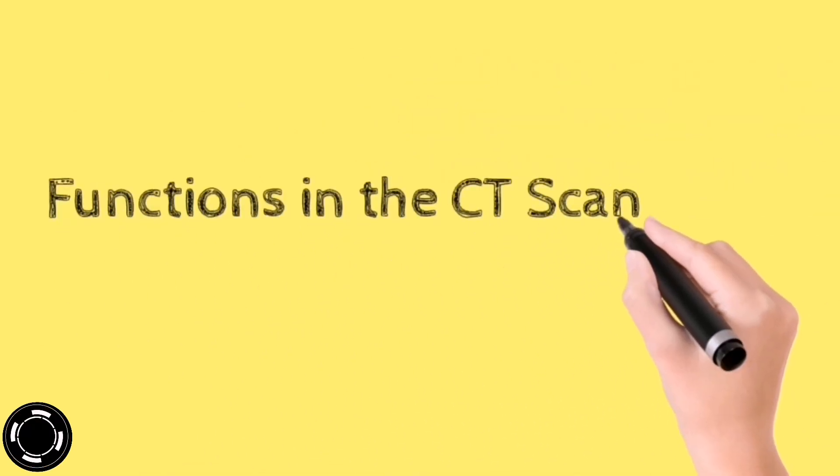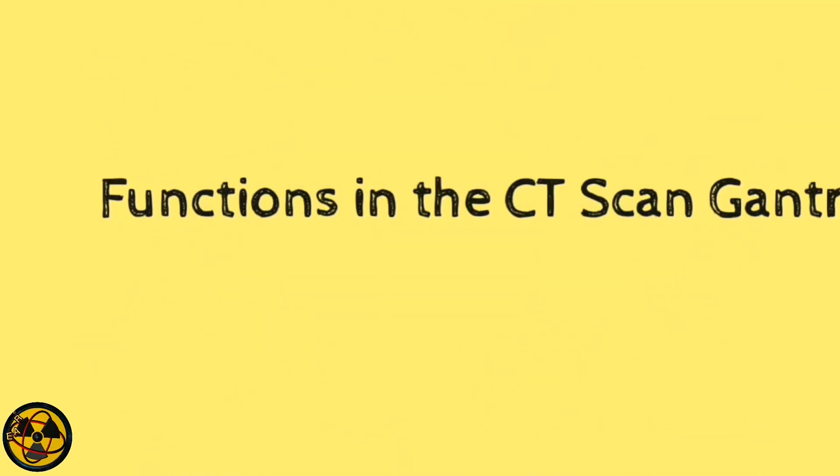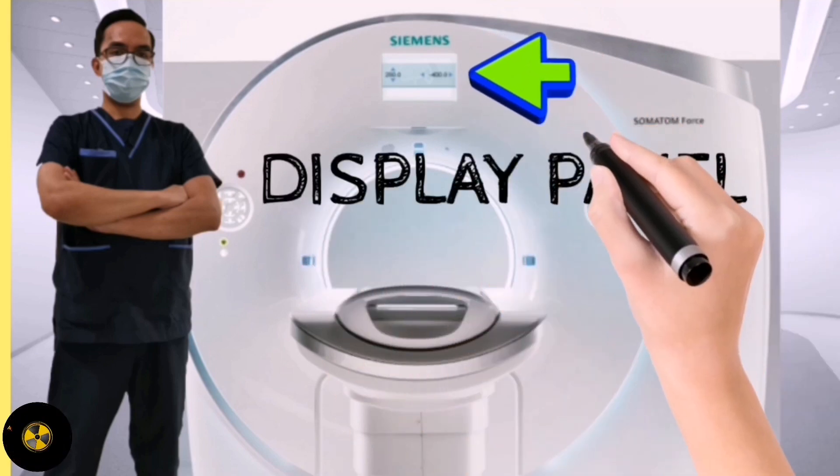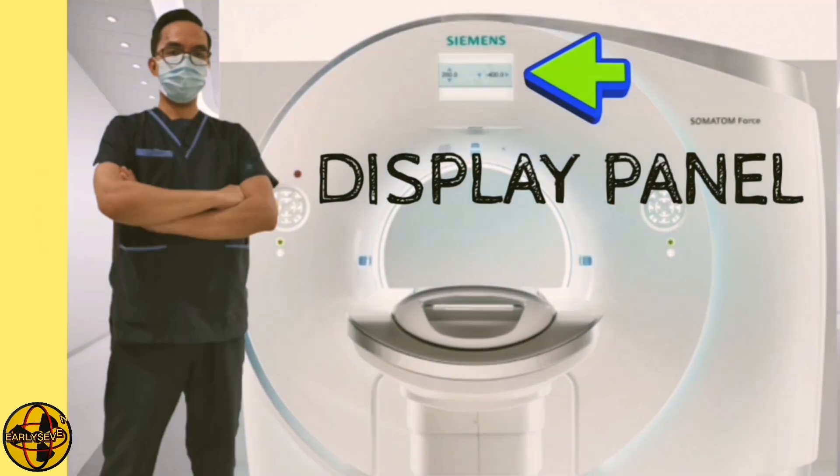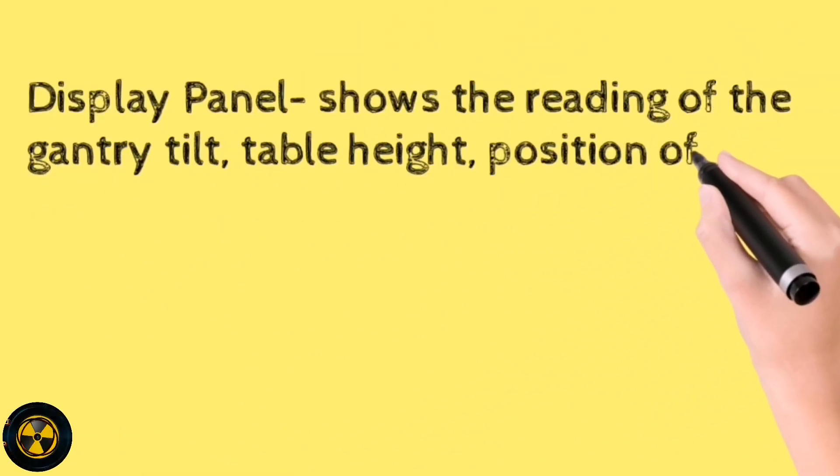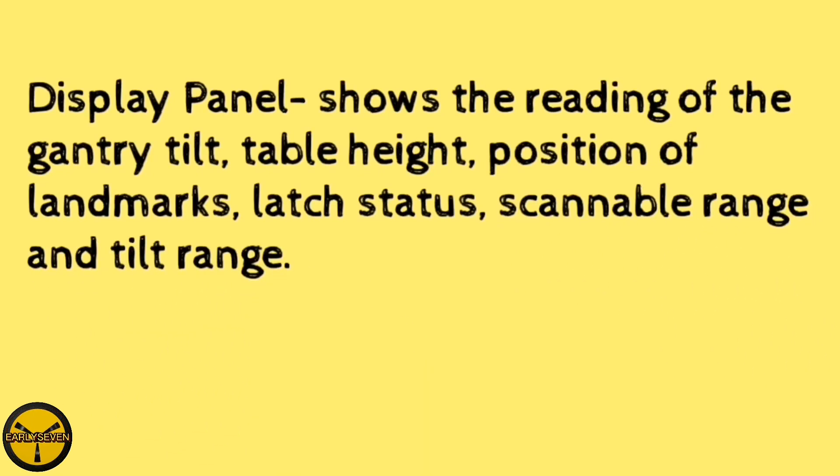What are the functions in the CT scan gantry? The first functions in the CT scan gantry is the display panel. The display panel shows the reading of the gantry tilt, table height, position of landmarks, latch status, scannable range and tilt range.